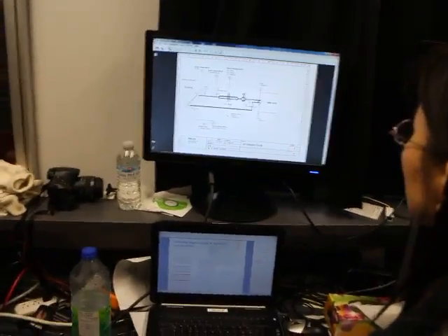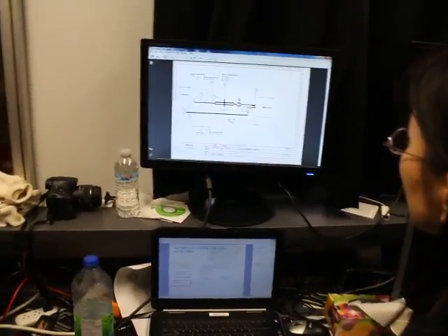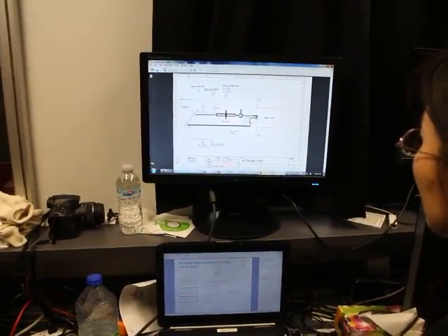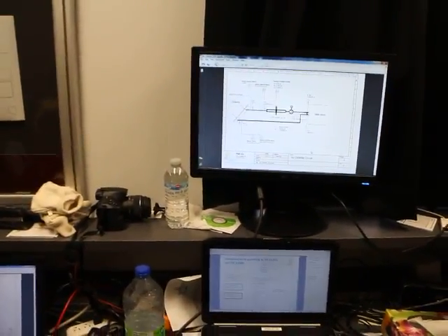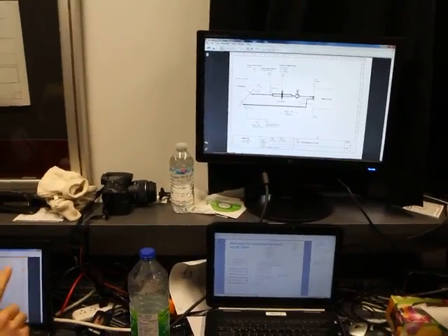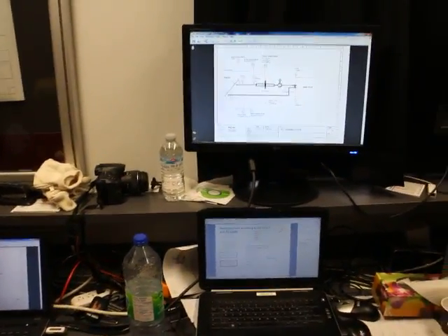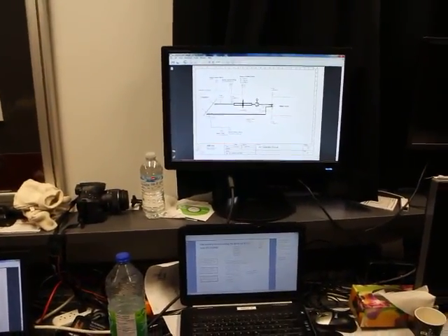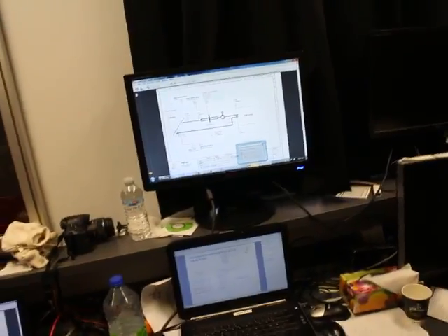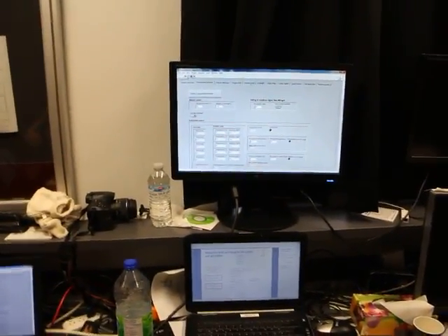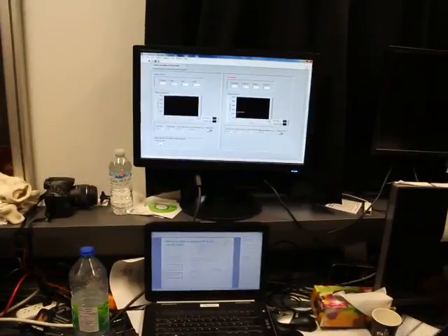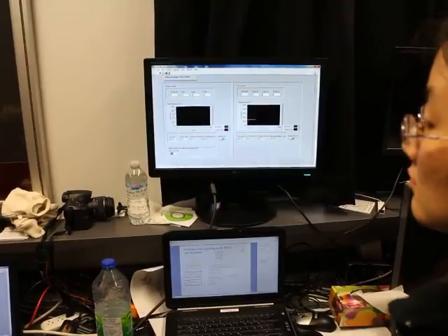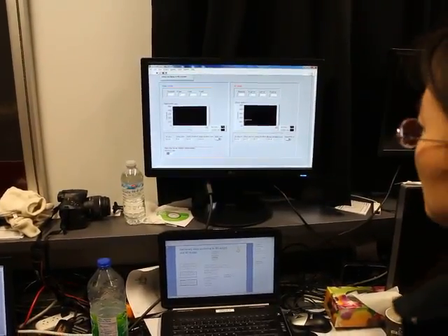It will not be exactly the same as on the outlet of the collector, but if you have a small mass flow in the water circuit, you will have a big delta T from the inlet over the heat exchanger. So what we do for that is, if you go to controller, you can see that the mass flow is 500. That's just to have a higher mass flow than regularly for collector testing.